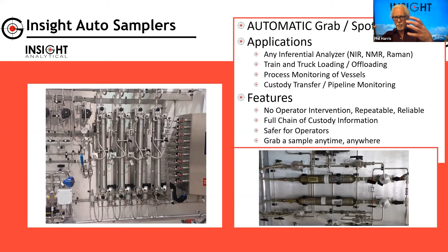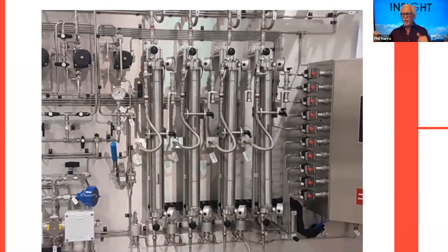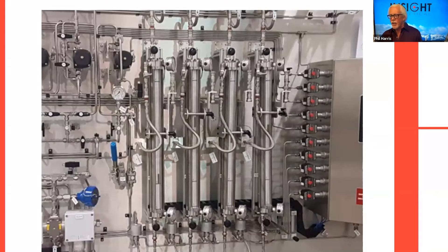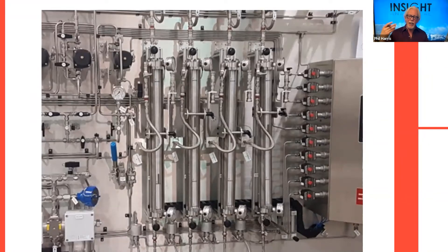The system shown here uses four floating piston cylinders for high vapor pressure samples. You can see a whole array of solenoid valves on one side controlling pneumatic valves on the other, and we completely control the fill cycle — how long it takes to fill and when we actuate it. We run all of that from a PLC so we get date and time stamp records, pressure measurements, and know exactly where the sample is from. We can even barcode each sample from the PLC interface, which gets around many of the problems commonly associated with pulling manual samples.